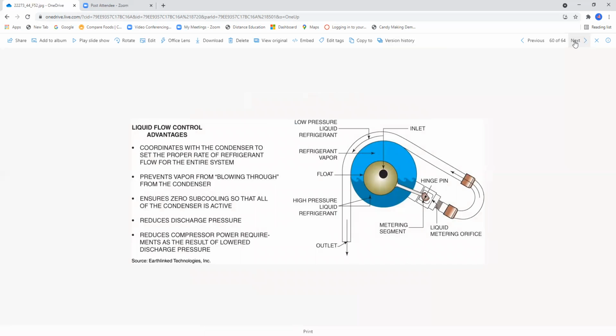Okay, here we have an interesting illustration. This is found on page 1352 of your textbook. And this is liquid flow control for your geothermal heat pump system. And the advantage is it coordinates with the condenser to set the proper rate of refrigerant flow for the entire system. So it's variable, prevents vapor from blowing through the condenser, ensures zero subcooling so that all the condenser is active, not just a part of it. Reduces compressor power requirements as a result of lower discharge pressure.